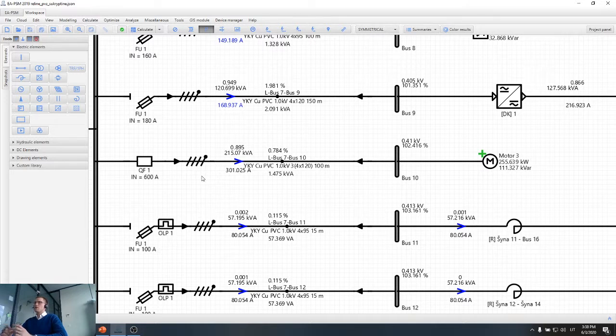Then there will be only 2 phases left with the other 2 fuses, and the motor will still operate, because if the motor is already started, 2 phases is enough for it to operate. However, there will be a huge asymmetry between the voltages, because one voltage will be equal to 0 and there will be 2 phases with nominal voltages. So when we use fuses we actually risk getting our motor overheated because of the huge asymmetry in phases.